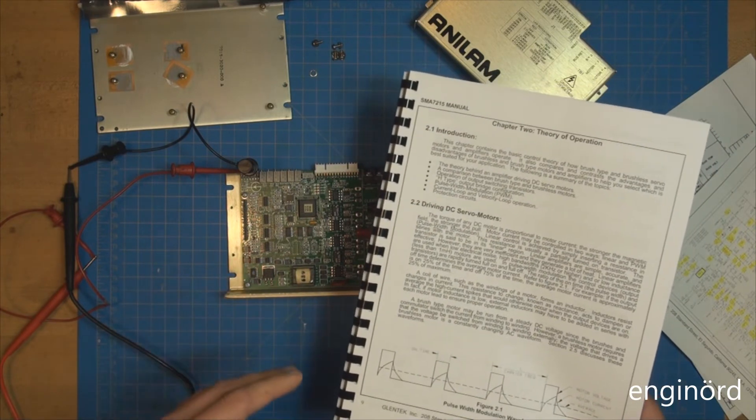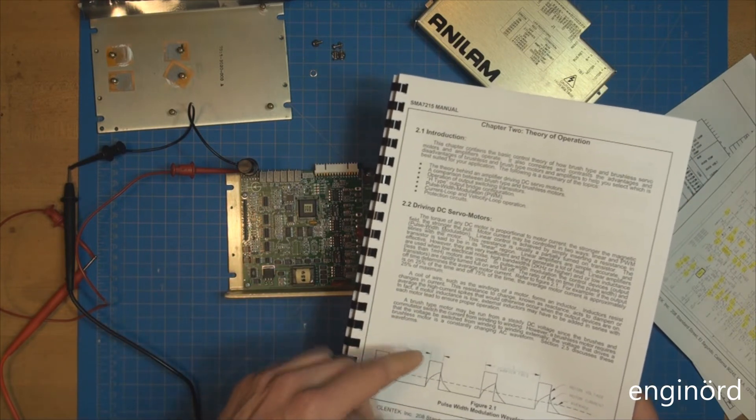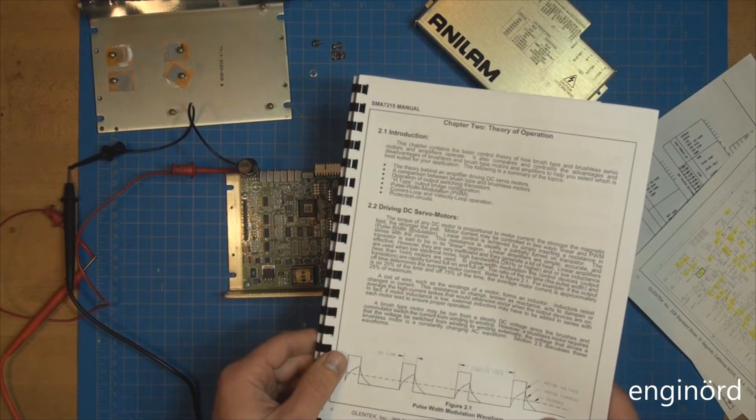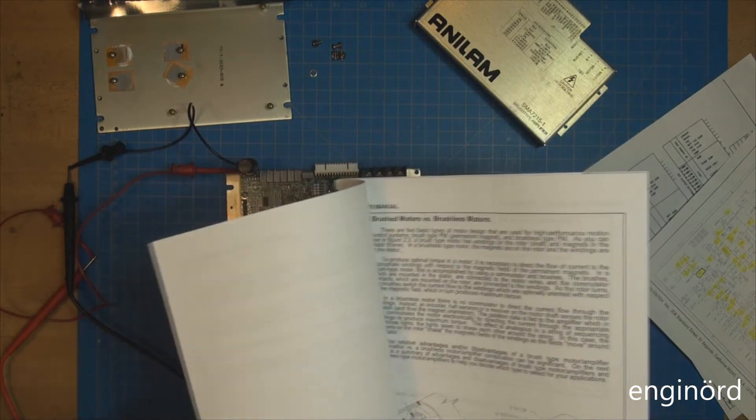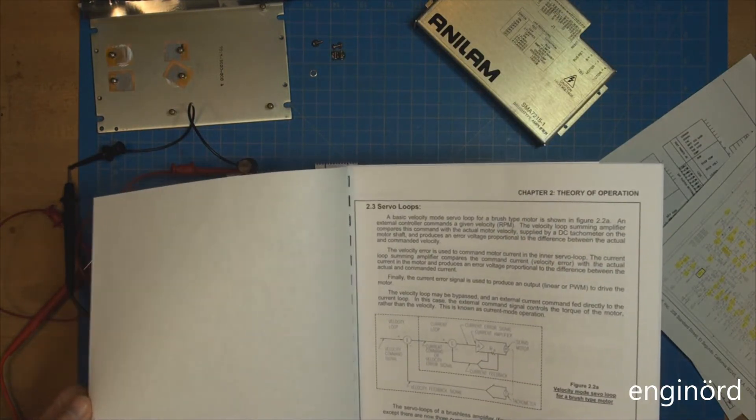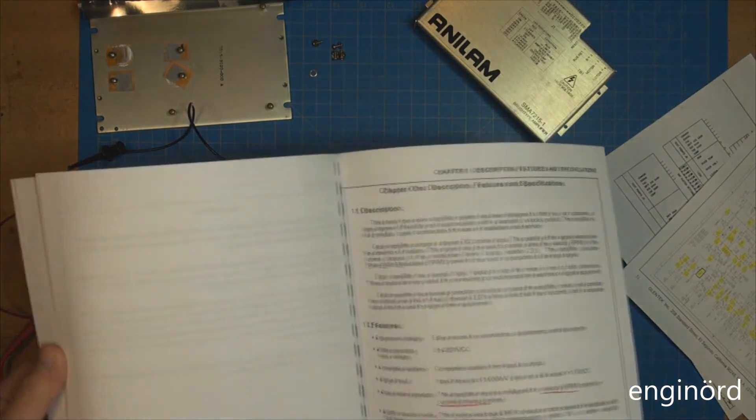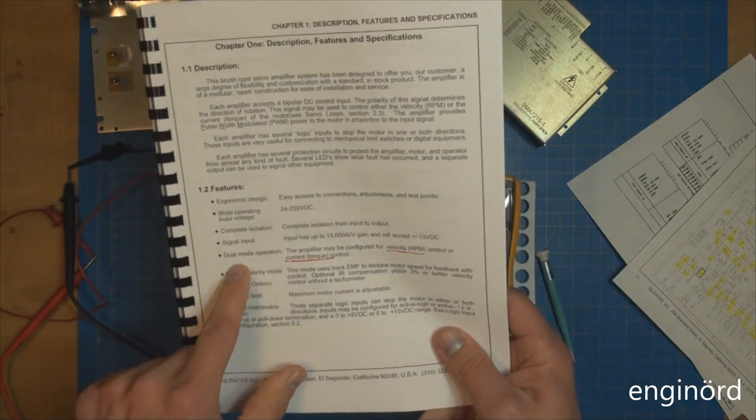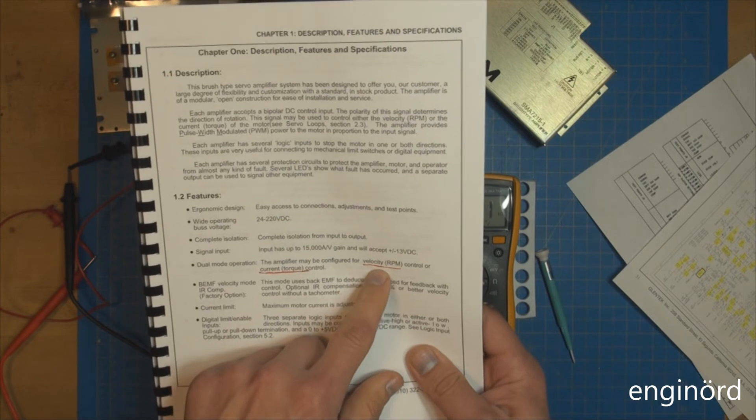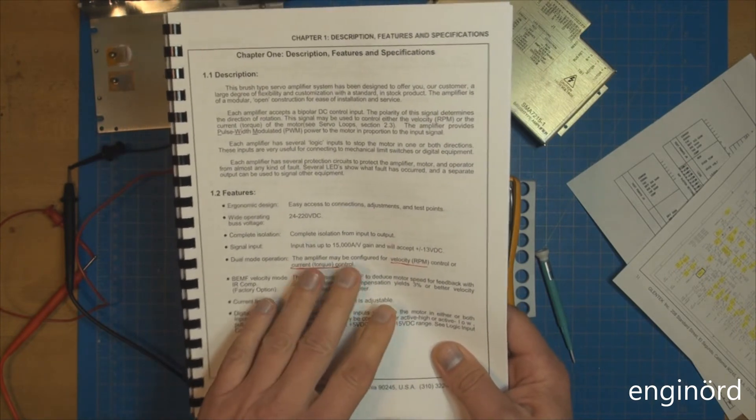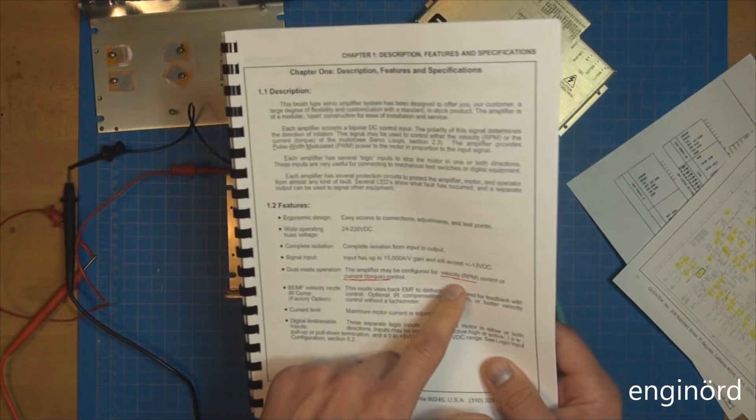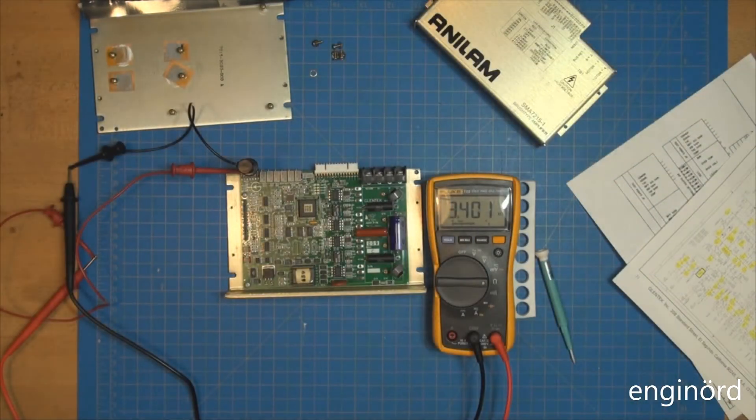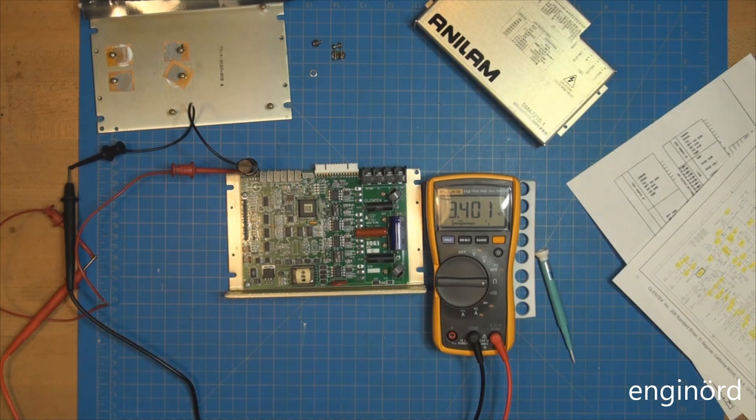It also has a tach giving feedback to the control, and the control based on the tach response can figure out the actual speed of the motor and make sure it doesn't overshoot whatever target it has. The manual says dual mode operation - the amplifier may be configured for velocity RPM control or current torque control. Right now I know these amplifiers are set up for velocity control, and these pots are part of the feedback system, the feedback mechanism.